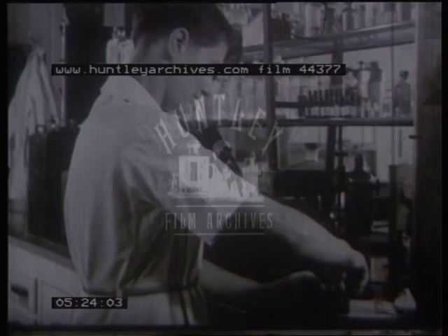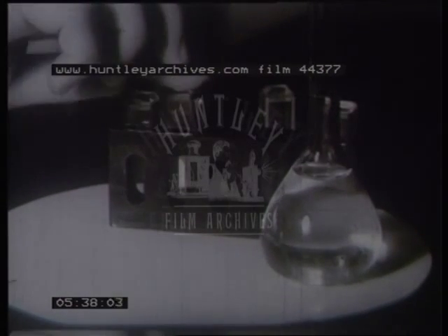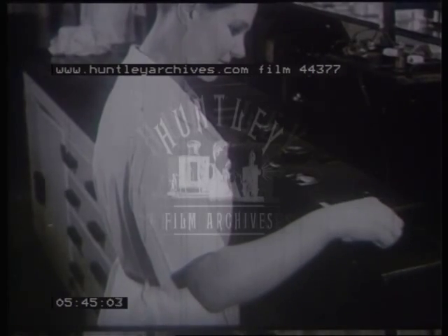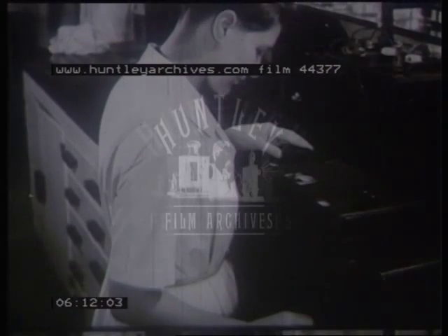The instrument used for this purpose is the photoelectric spectrophotometer. The rack containing quartz cells is removed. A sample of the vitamin solution under test is poured into a fresh cell and inserted into the rack, which is then replaced. With a blank cell in the beam, the wavelength of 328 millimicrons is selected and the control adjusted so that the needle on the dial is at zero. On bringing the vitamin solution into the beam, the current falls. It is compensated by a further current, controlled by a dial which is calibrated to read the percentage of light transmitted. From this, the amount of vitamin A present can be calculated.